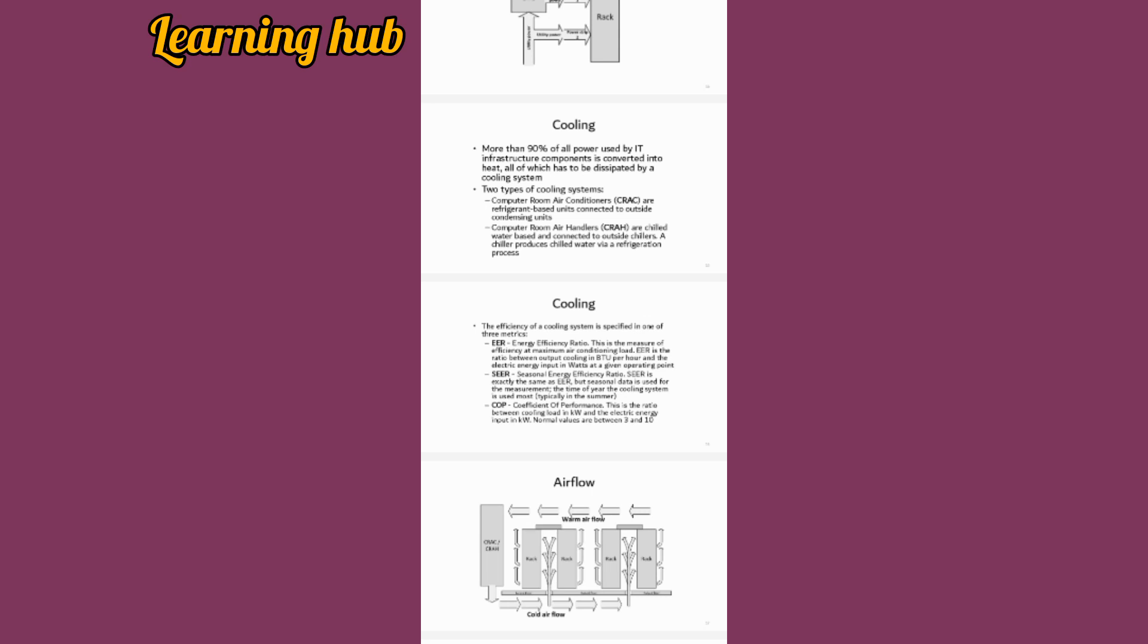COP, coefficient of performance, is the ratio between the cooling load in kilowatts and the electrical energy input in kilowatts. Normal value is between 3 and 10.